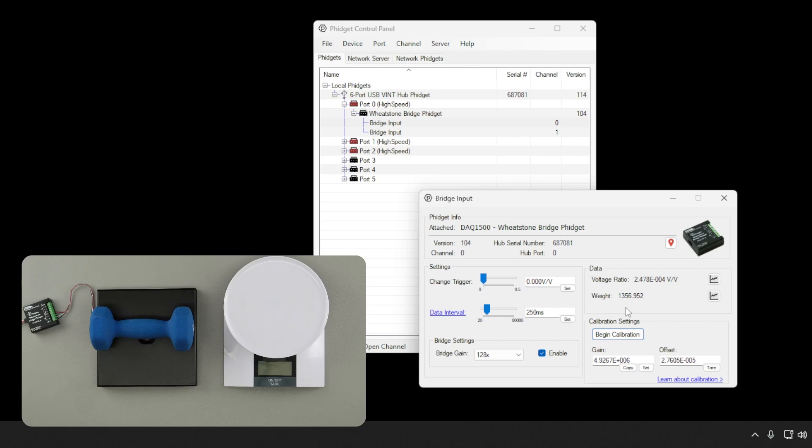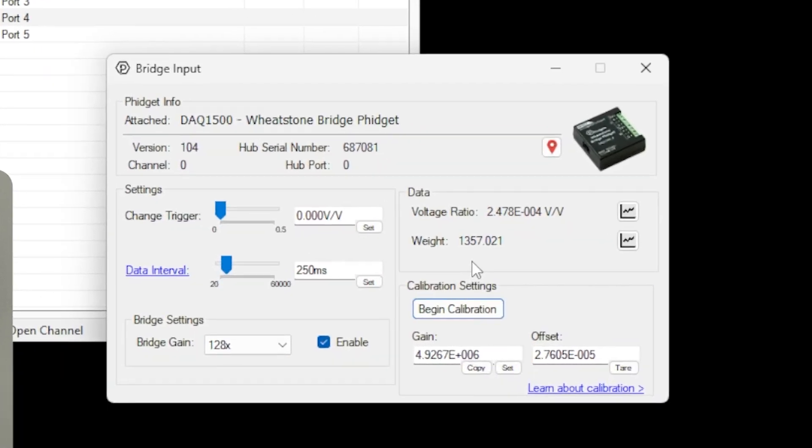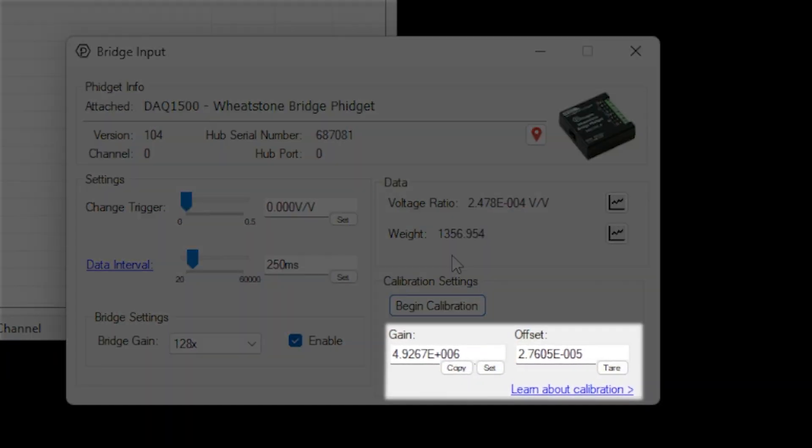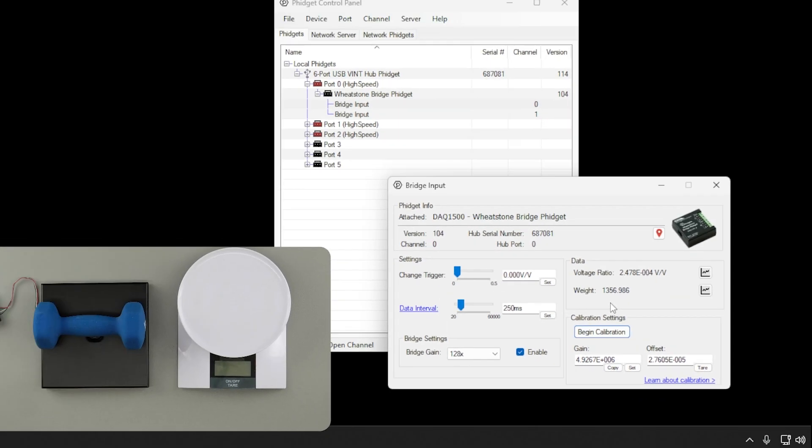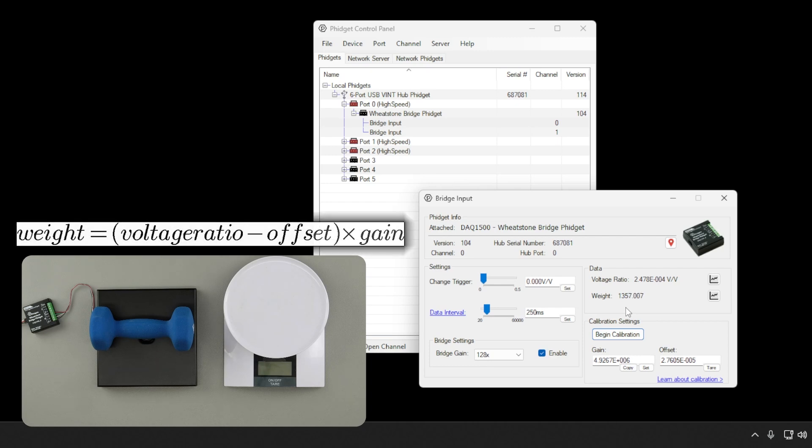This program provides two calibration parameters: gain and offset. You'll need to use these parameters in your own software to calculate weight with the following formula. As we can see from the formula, the offset is removed from the raw voltage ratio, and the gain is then applied to convert from units of volts per volt to the units used during calibration.